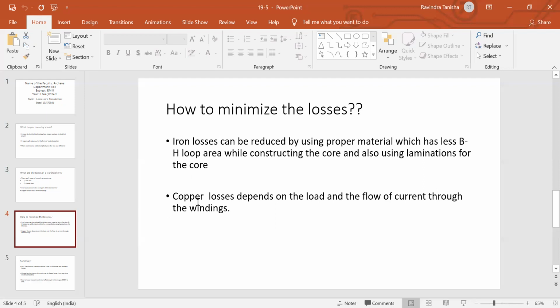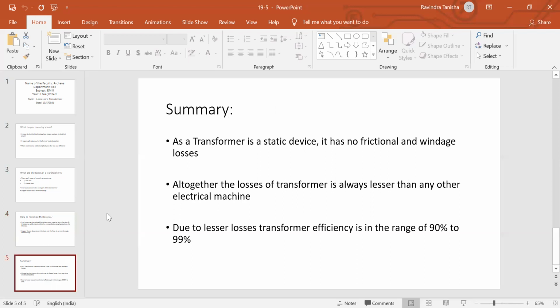Then what about the copper loss? Copper loss depends on the amount of load current flowing through the winding. So if you can minimize the flow of current, then automatically we can reduce the copper losses as well. Then what is the summary of these losses? As we have already discussed, the transformer is a static machine. When it is a static machine, it has no rotating parts, so there is no need to worry about friction and windage. There are no frictional and windage losses associated with the transformer, being a static device.